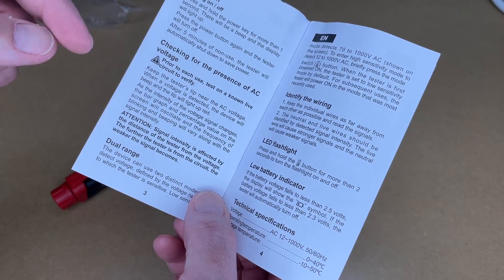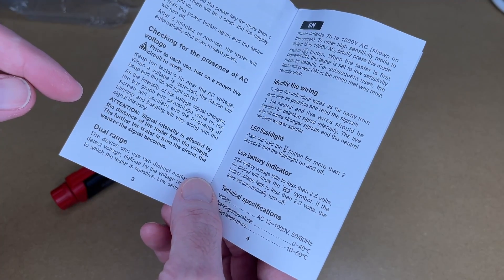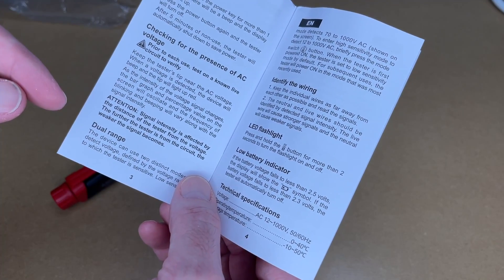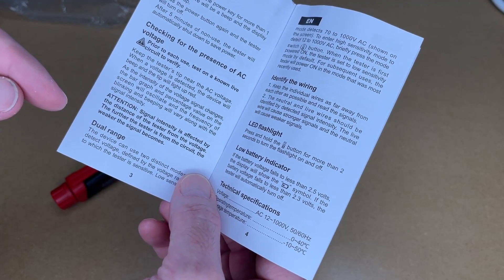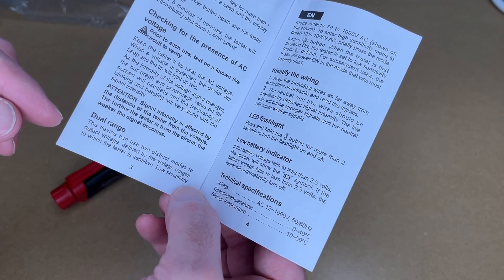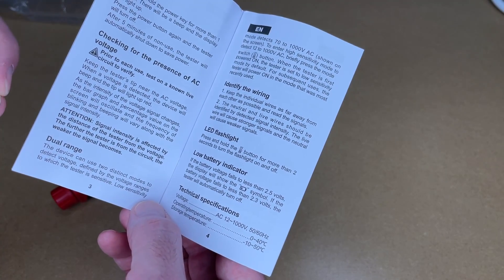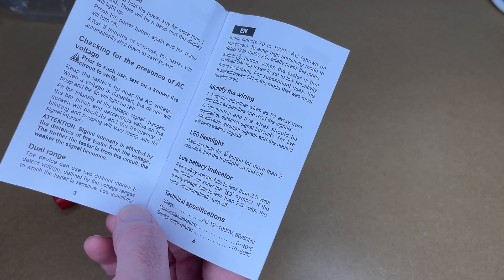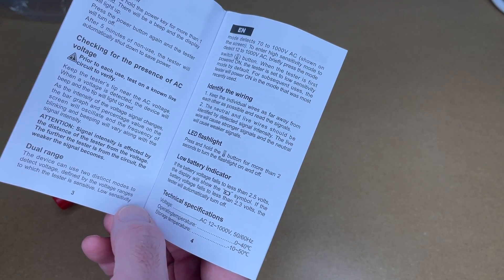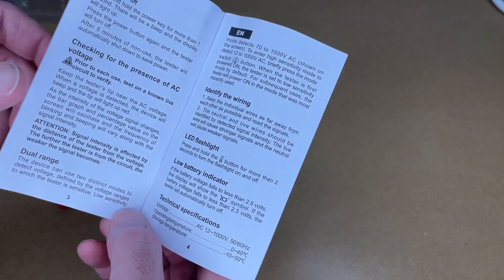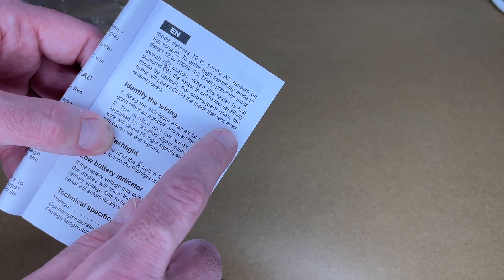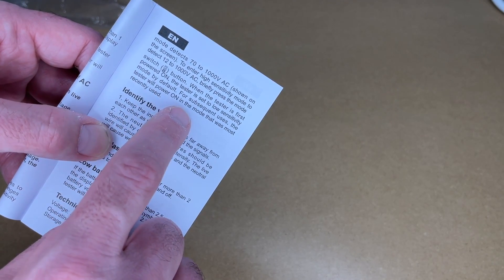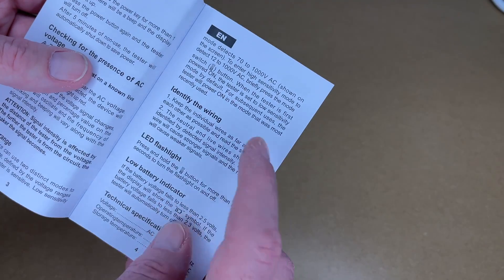You will want to read the whole manual. It says the signal intensity is affected by the distance of the tester from the voltage. The further the tester is from the circuit, the weaker the signal becomes. So this is dual range. It detects 70 to 1000 volts AC. To enter the high sensitivity mode to detect 12 volts to 1000 volts AC, briefly press the mode switch button. So the default is the low sensitivity mode. And then it says for subsequent uses, the tester will power on in the mode that was most recently used.